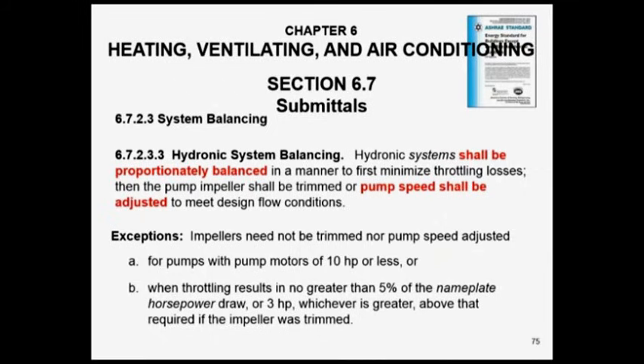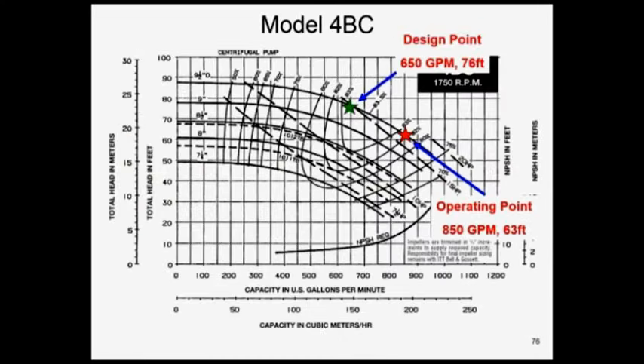So what we're after is operating costs. On the bottom line, this is an energy code. We're trying to reduce energy. And that means we don't want that combination throttling valve being throttled back. It's nice to have it around, but we don't want it throttled back when we wind up with a true balance. So let's go back to our example. We're now back at the green point because we throttled it. We went to 650, 76 by throttling.